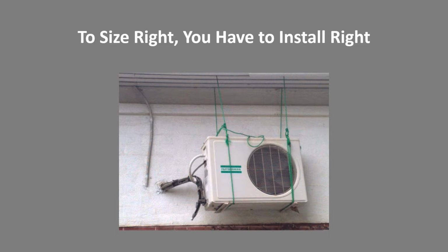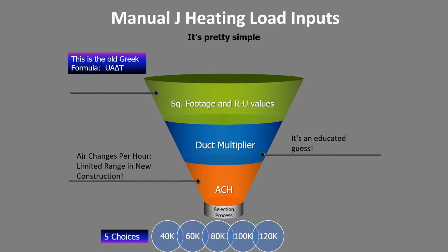I know you probably all have the Hall of Shame photos from your competitors' shops that they installed. Manual J heating loads, it's really pretty simple on the heating side. It's that old Greek formula, if you will. It's UA delta T, or the U value, times the area of the basics of the building's components, times the delta T.